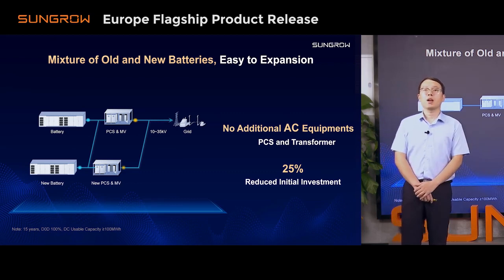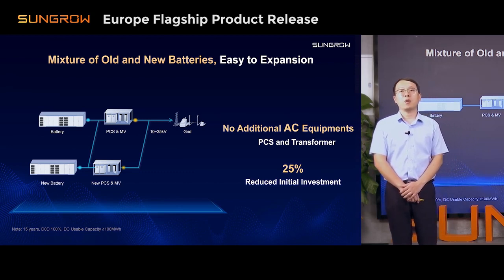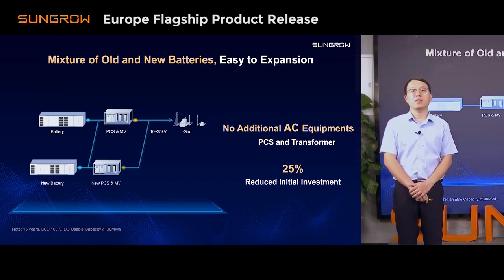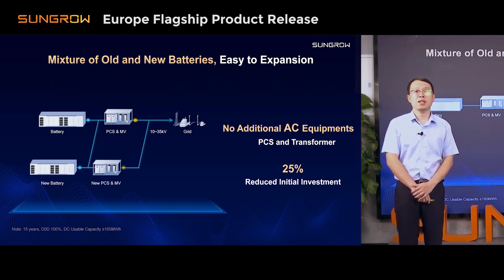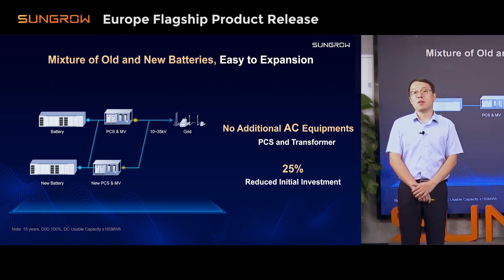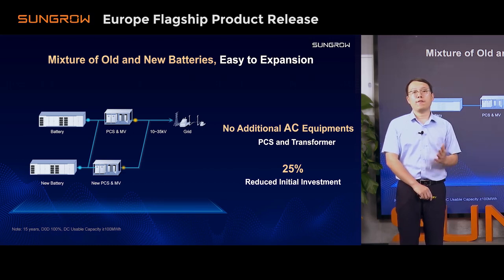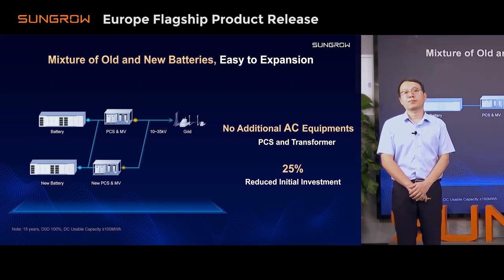What's more, when we design the solution for battery replenishment in the future, it will be much easier. There is no need for SOC calibration after battery replacement or maintenance. Cluster level management allows us to configure the battery rack with 5 or 6 modules, and racks with these 2 different numbers of modules can be mixed in use.